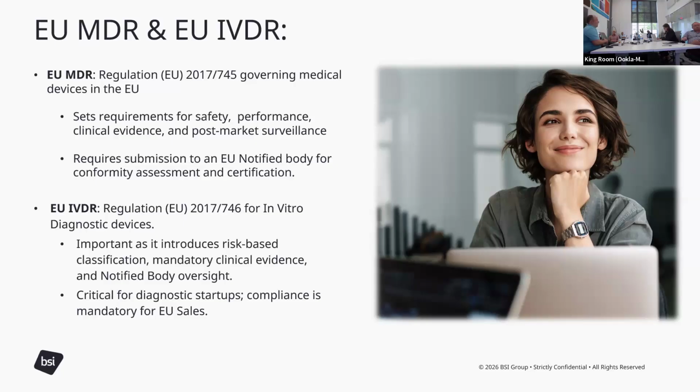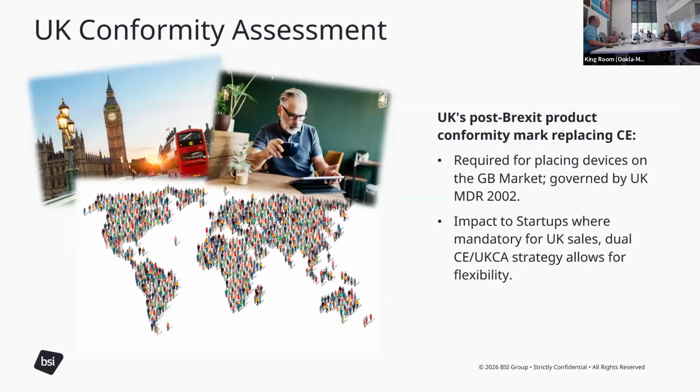Does it perform clinically? You do have to get a submission to an EU notified body to have this done. There's a list of notified bodies. There's probably around 30 at this point. BSI probably has 30% of the certificates, so we're one of the largest notified bodies. Now, I'll talk a little bit more about that process as well.